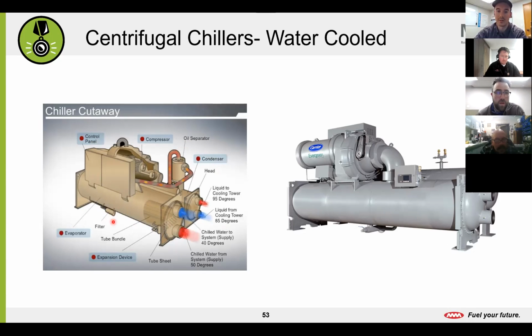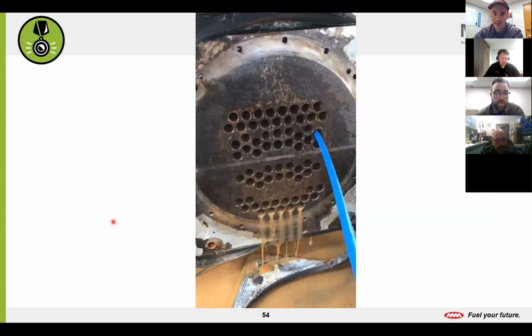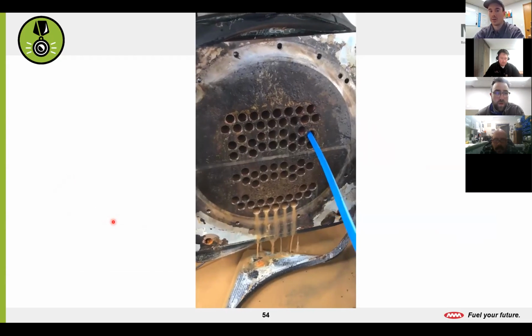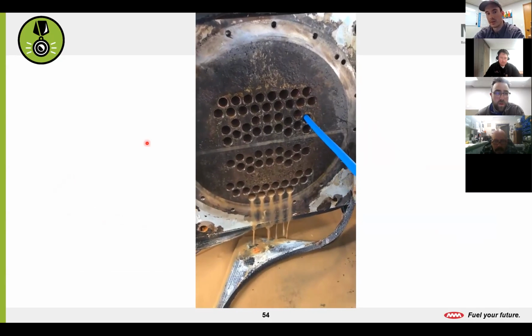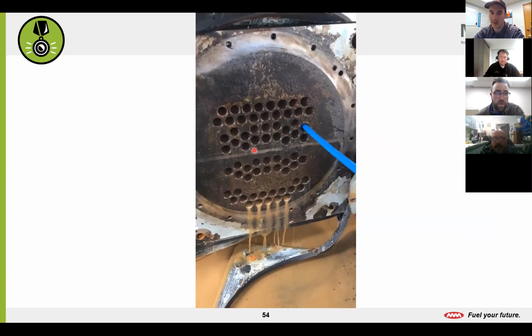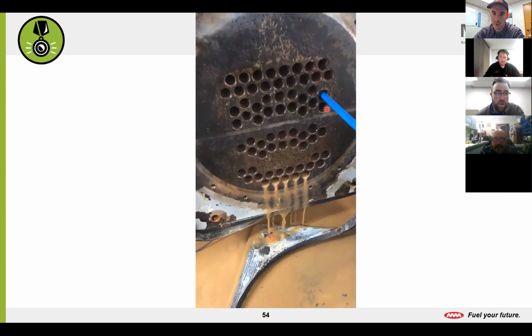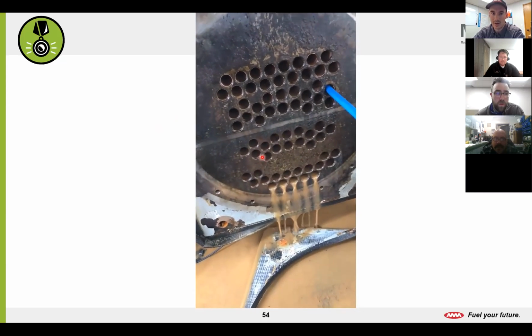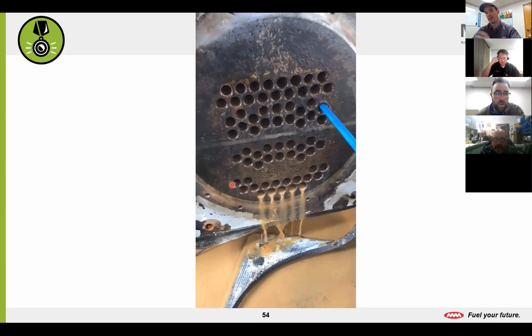Yeah, they're going to look a lot different. They do require some different maintenance items than an air-cooled chiller. With an air-cooled chiller, you have to keep that condenser coil clean, make sure we got proper heat transfer through it. On these guys, we'll show you here. This is one of our technicians. Tube punching is what they call it. So these tubes are where water flows through, and actually in that barrel, you're going to have refrigerant surrounding it.